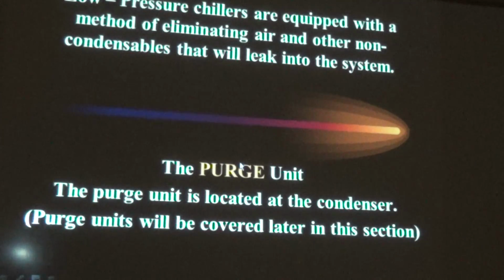Low pressure chillers are equipped with a method of eliminating air and other non-condensables that will leak into the system. That method is the purge unit. And this is the test question here. The purge unit is located at the condenser. So the purge unit is actually mounted to the top of a condenser.